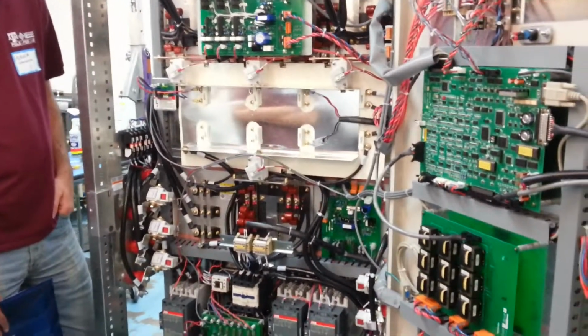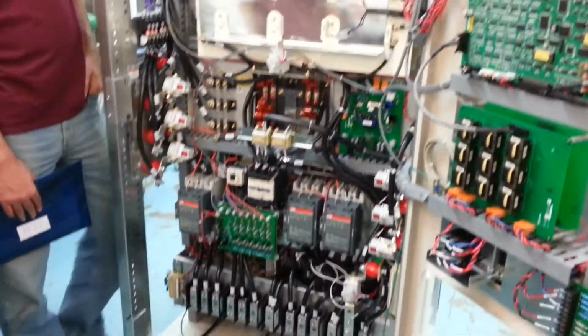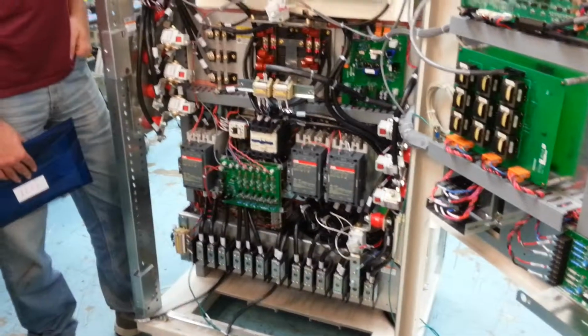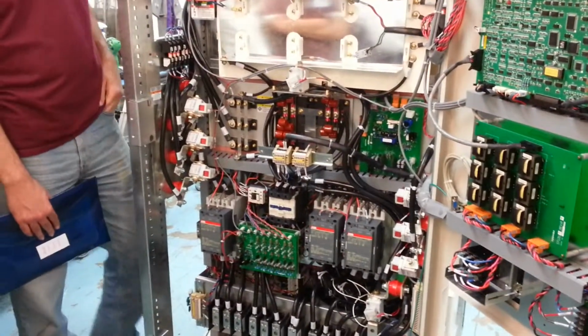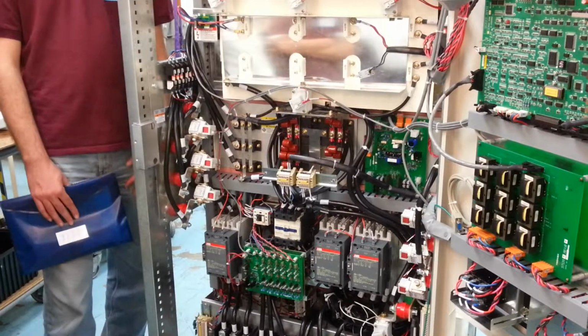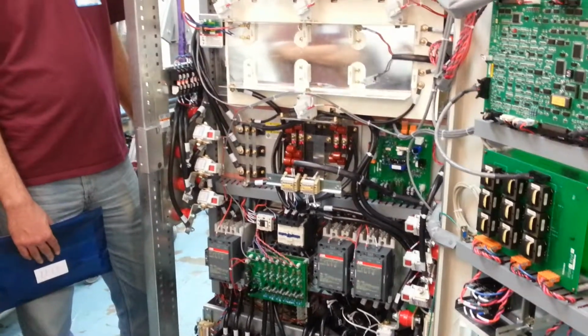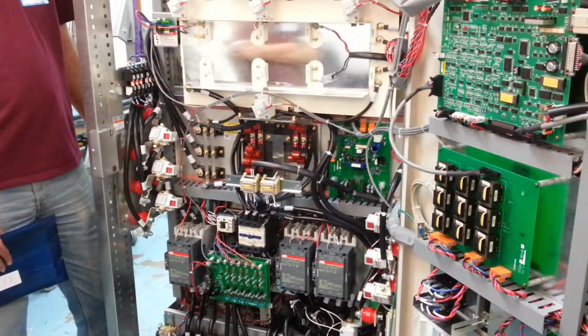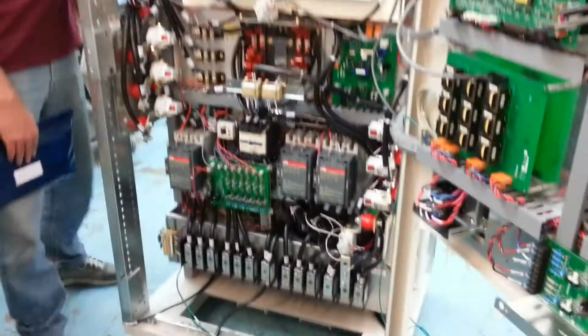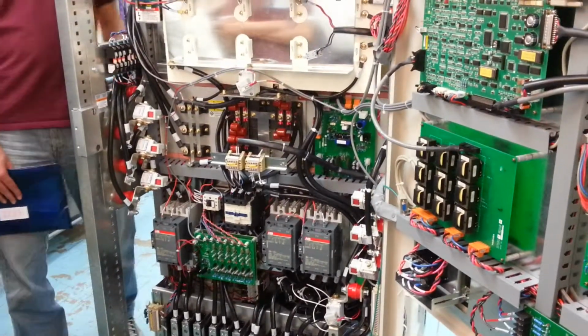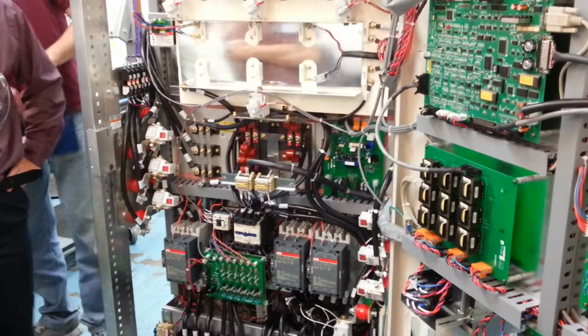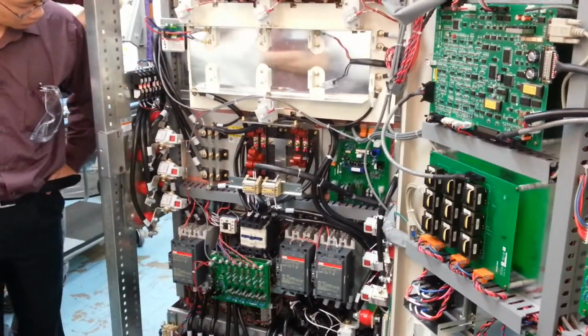Those ABB ones, what are those? Contactors. Input contactor, bypass contactor, output contactor. Yep. And then, of course, fuses for input and output. And in the center there is your DC chopper. DC connections are on the bottom, DC chopper in the center. So that'd be where your battery cabinet hooks up. Yep. When it's in battery backup, the battery chopper chops it up to the DC bus voltage.